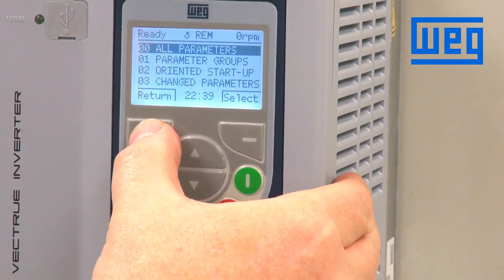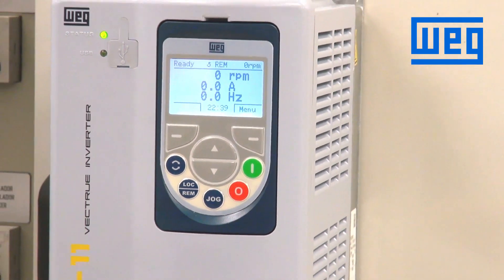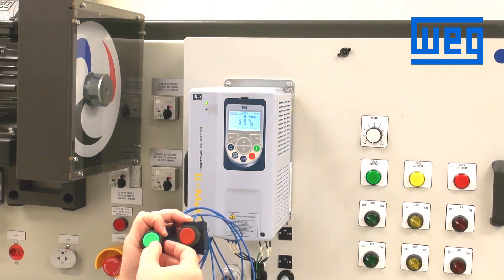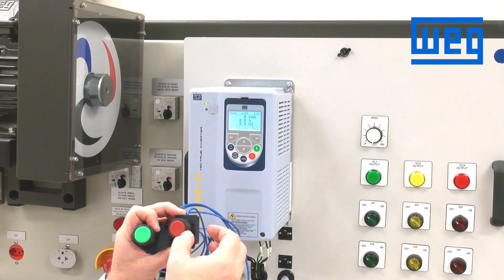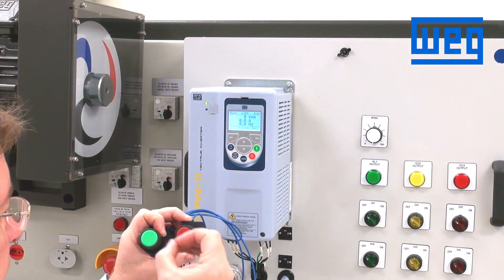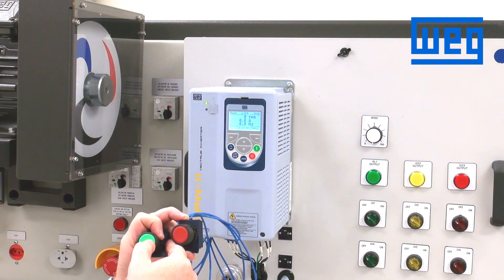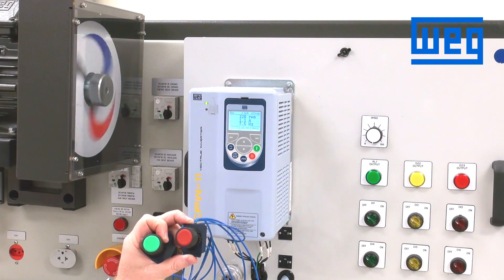Return back to the main display screen. This should work using the start and stop buttons. A normally open contact on digital input one is for start — momentarily close it and the drive should run. We close that contact and it should run. Press start — the drive is running.